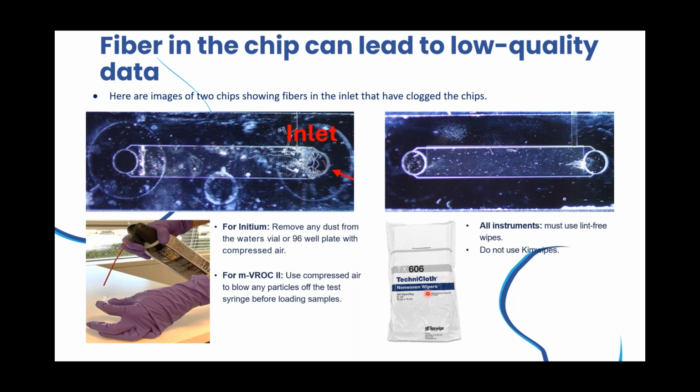And if you need to wipe something from the instrument, that's when we recommend you use the lint-free wipes. Whenever I visit customer sites, I often see Kim wipes near the instruments, so I always make sure to inform our customers not to use these Kim wipes.